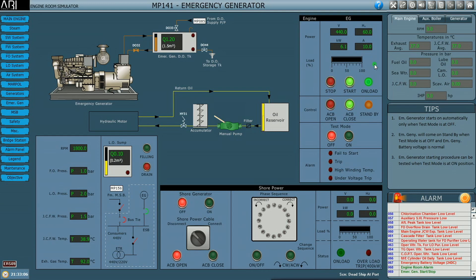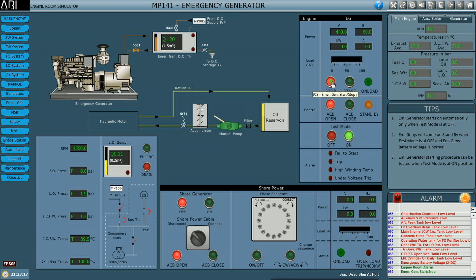What we saw now was the battery starting mechanism. Now I'll open the ACB, take the generator off load, keep the test mode on, stop the engine, and simulate how to start manually using the hydraulic oil pressure. There is an oil reservoir and a manual pump and an accumulator.